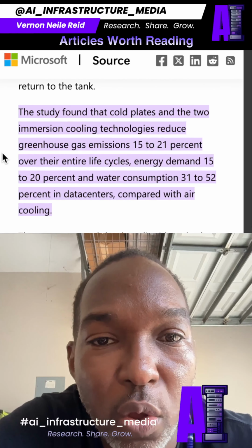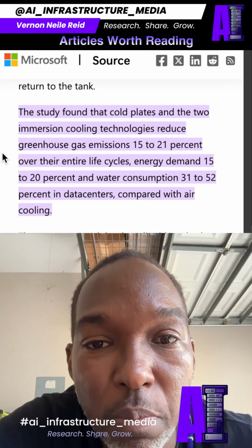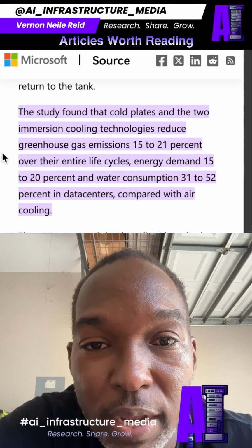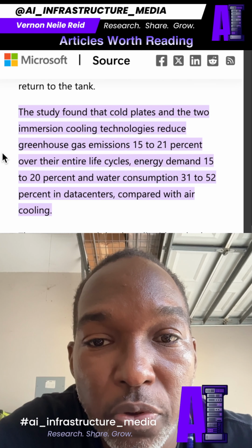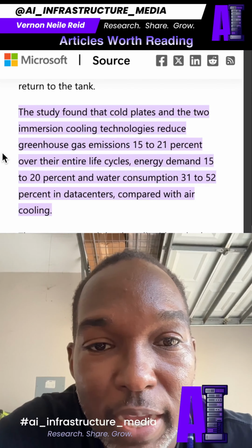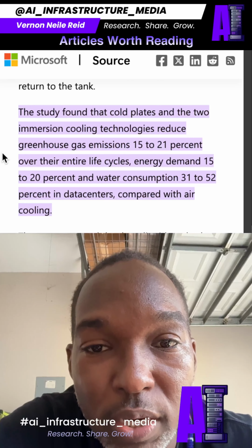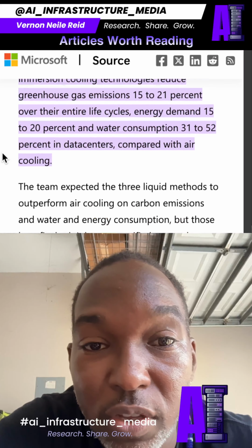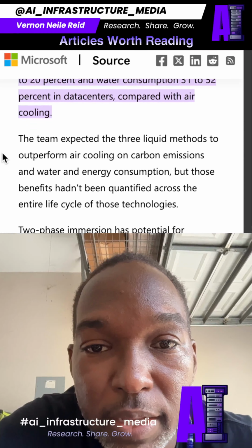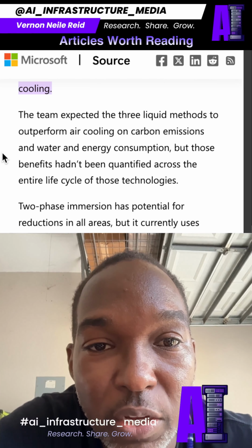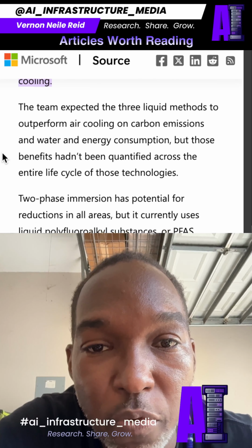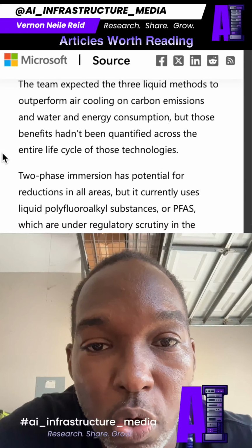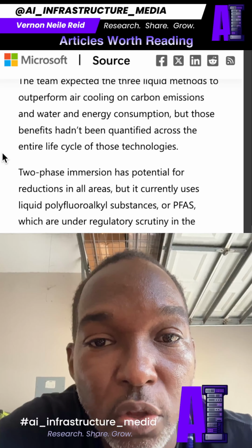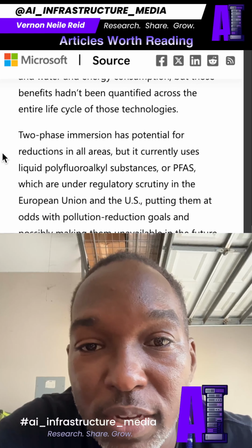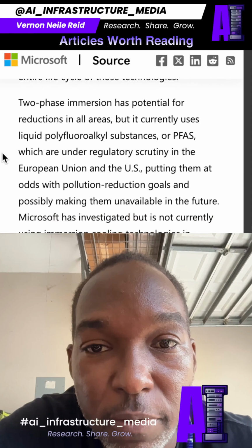The study found that cold plates and the two immersion cooling technologies reduce greenhouse gas emissions 15 to 21% over the entire life cycle, energy demand 15 to 20%, and water consumption 31 to 52% in data centers compared with air cooling. The team expected the three liquid methods to outperform air cooling on carbon emissions and water and energy consumption, but those benefits hadn't been quantified across the entire life cycle of those technologies.